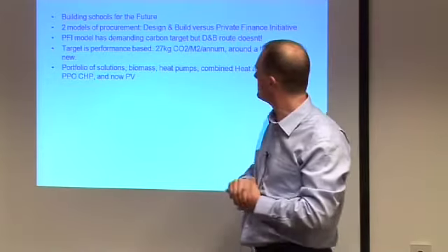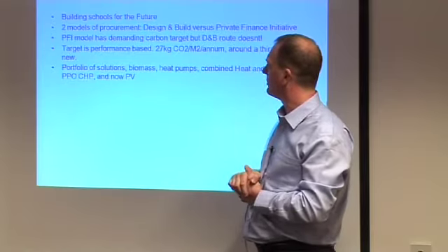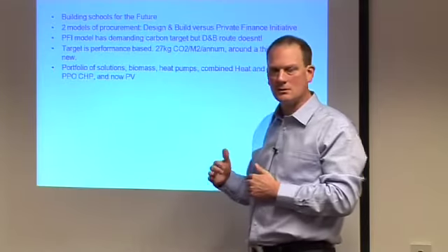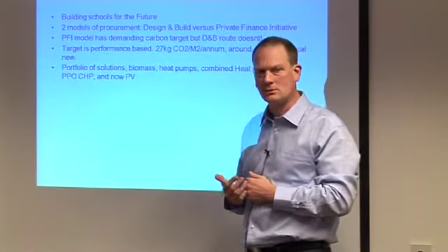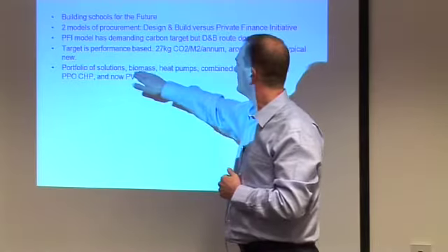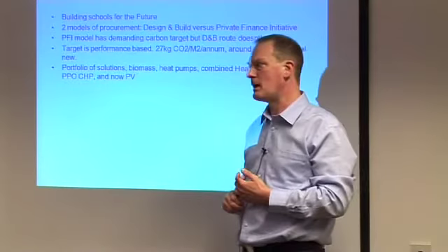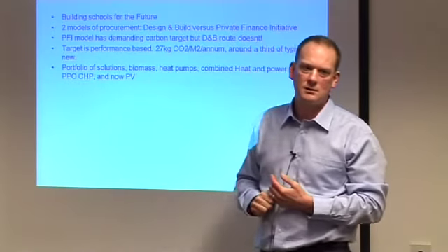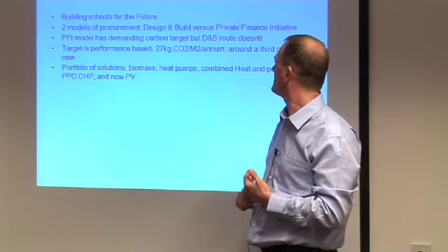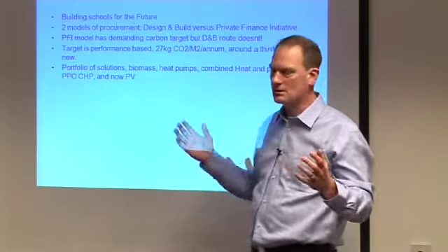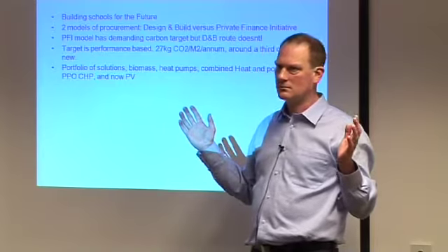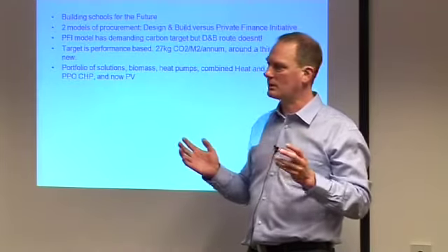Some of the solutions are being installed very badly, and therefore going wrong, and it's quite evident that the industry that's building schools does not understand a lot of the technologies, and there are major construction companies or major consulting companies that are doing this and making these mistakes. So biomass is completely oversized and runs a couple of hours a day and then jams up, and people wonder why it goes wrong.